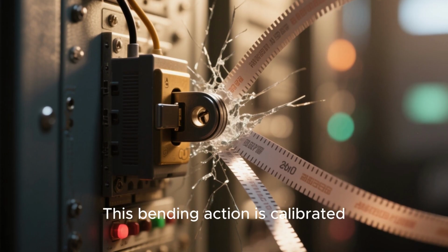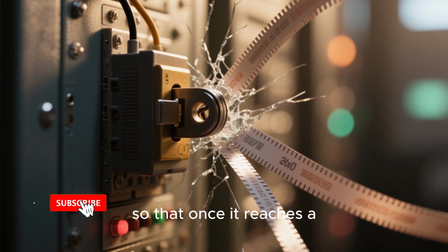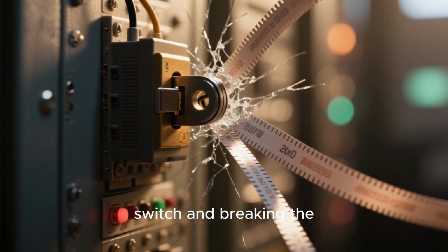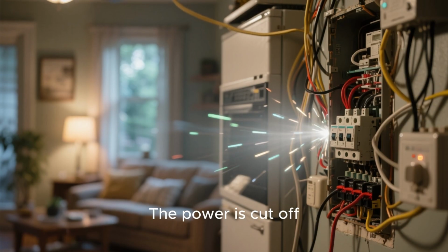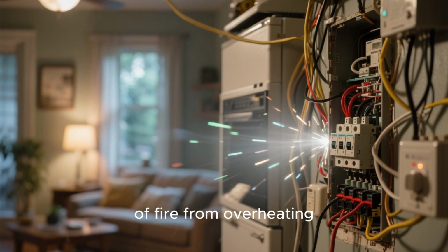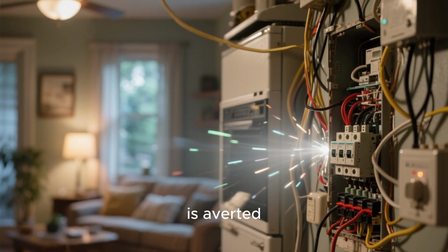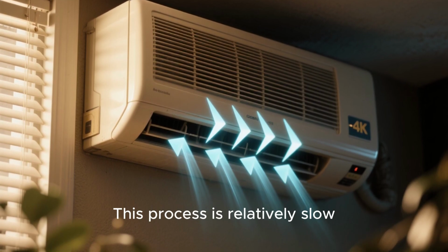This bending action is calibrated so that once it reaches a certain point, it physically trips a latch, releasing a spring-loaded switch and breaking the circuit. The power is cut off, and the danger of fire from overheating is averted. This process is relatively slow.